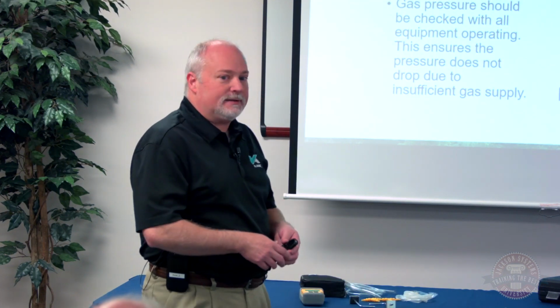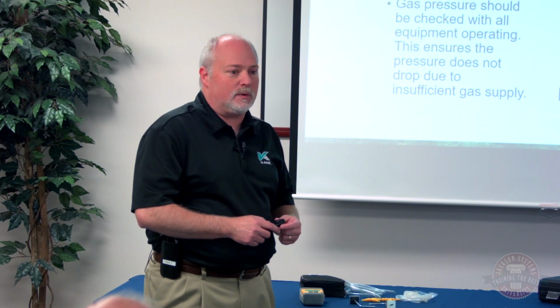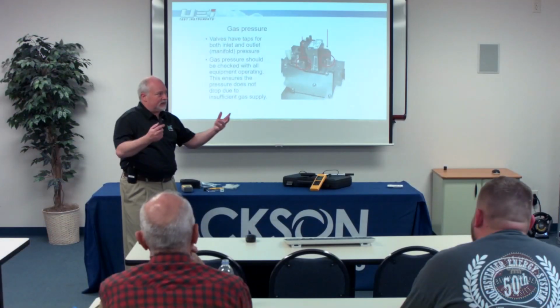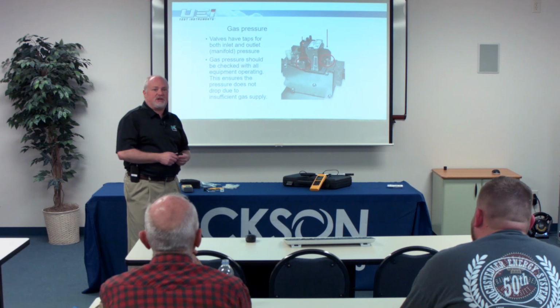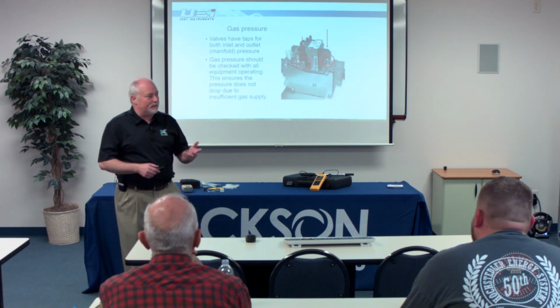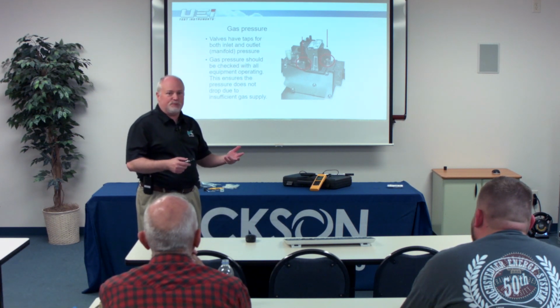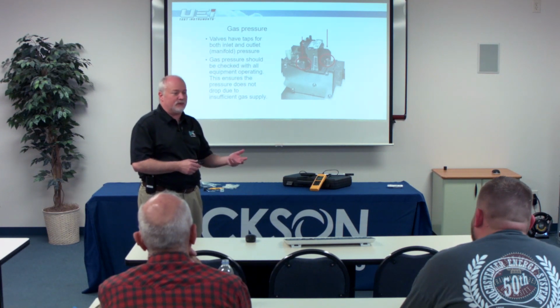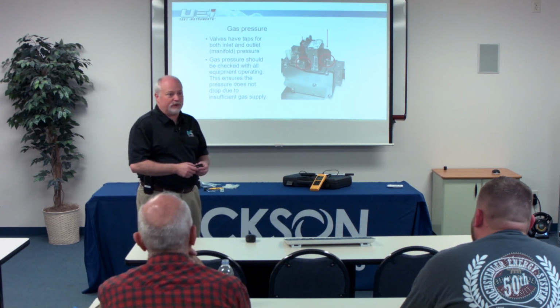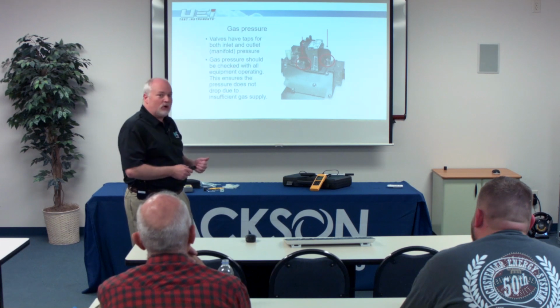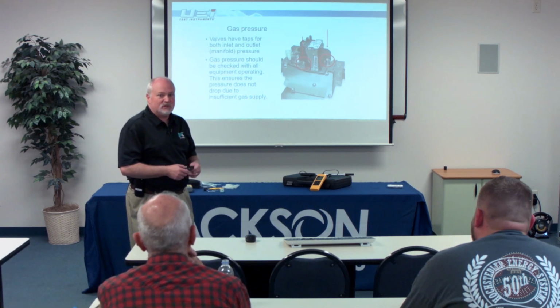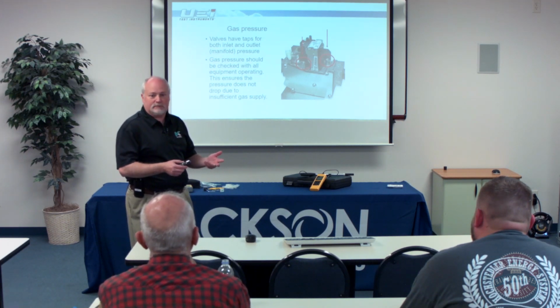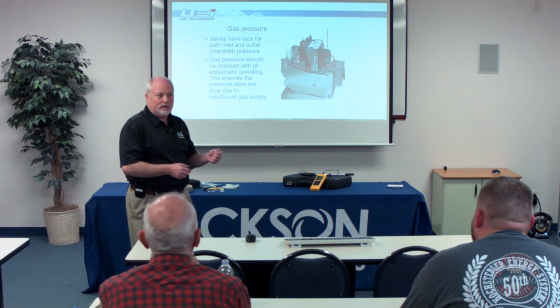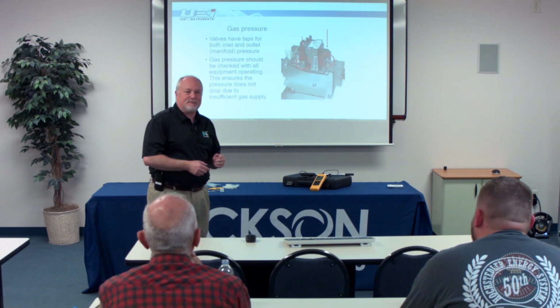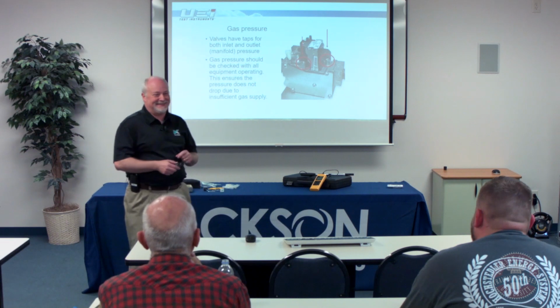Great example of that, had a customer with one of our equipment lines that we represent, said, man, these heaters are firing, but we're just not getting much output from them. Stopped by, the technician assumed that, hey, the appliance was lighting when running. He figured everything was operating okay. Well, when the equipment was off, we put a manometer on it. He had 11 inches of propane gas pressure. When the equipment started up, pressure dropped to less than 3 inches.